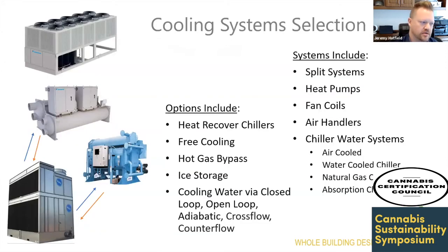Next, cooling system selection—this could be a 5-hour topic by itself, so I'll move through it quickly. Systems you'll likely see in cannabis include split systems—and not just small mini splits like in an IT closet, there are many different types—heat pumps, fan coils, air handlers, chilled water systems, and more. Many manufacturers in this industry make equipment specific to cannabis, because traditional equipment, like what you'd get for an office, is tuned to a higher sensible heat ratio, whereas cannabis requires a very low ratio.